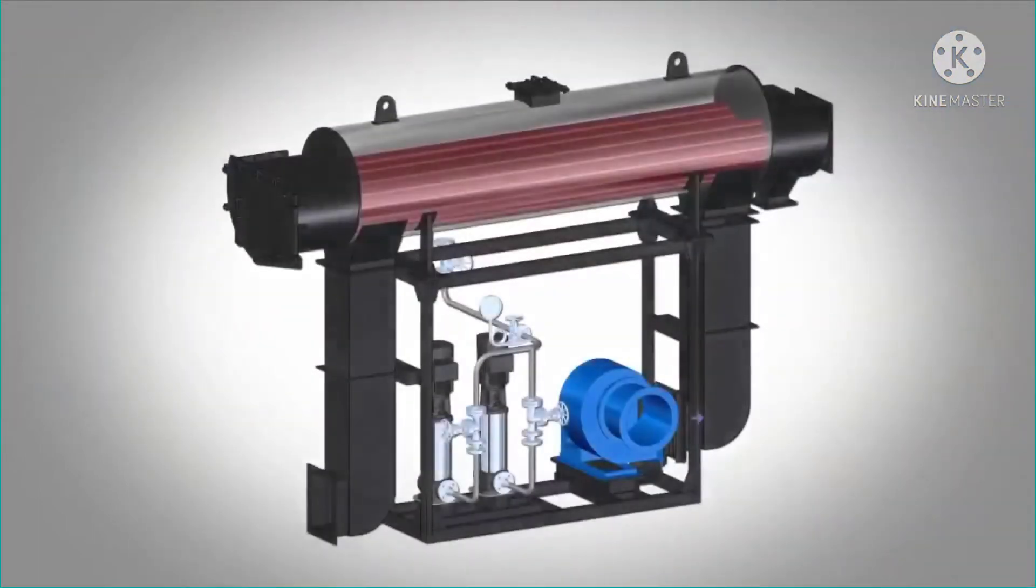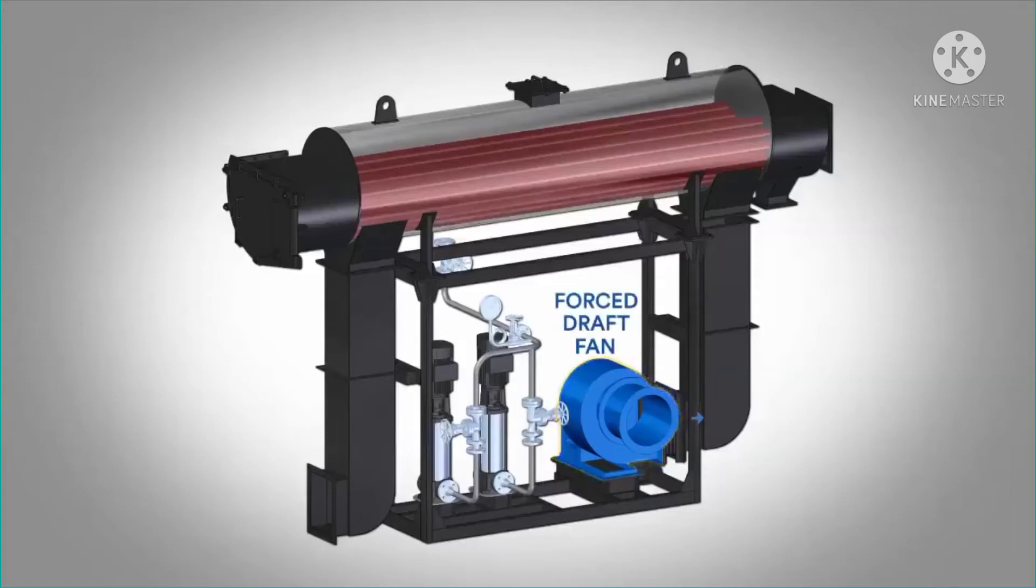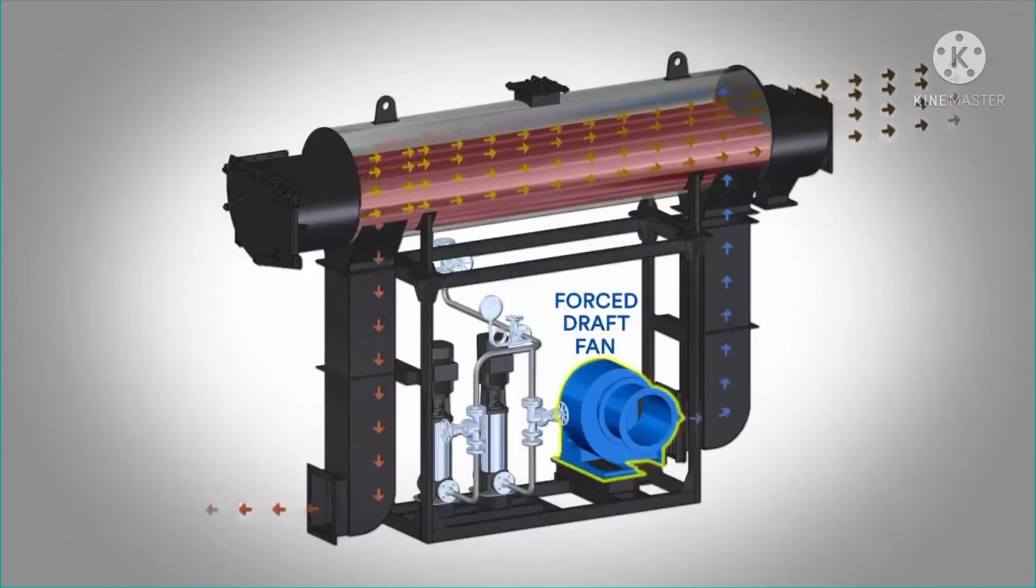Comblock has a balanced draft system of transporting the combustion air and flue gases. In this method, a forced draft (FD) fan pushes the air required for combustion to the combustion chamber through air ducting. The flow of air can be controlled by dampers.